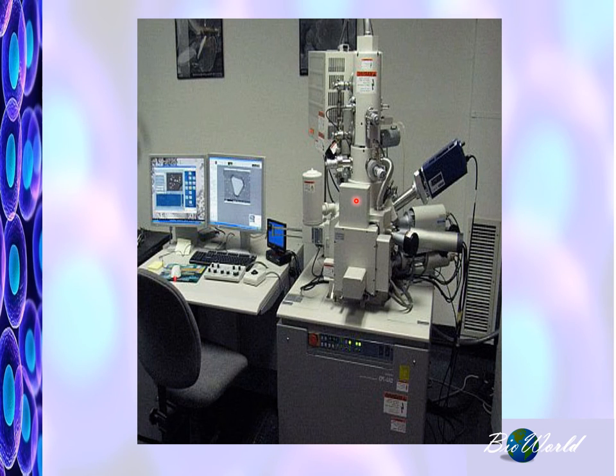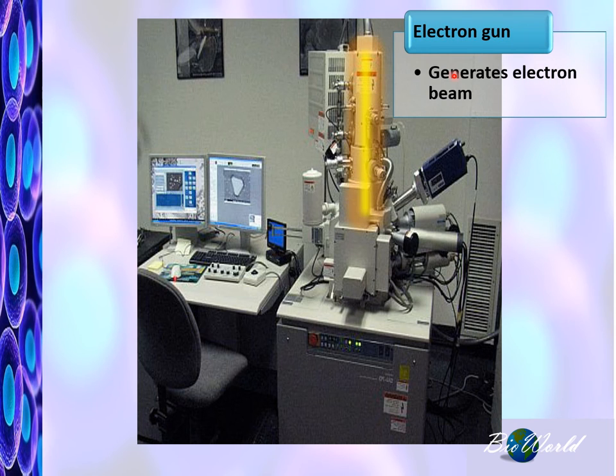The scanning electron microscope in the early stages is similar to the transmission electron microscope. So when you switch it on, an electron gun will generate the electron beam. That electron beam will contain electrons traveling at high speed. So this column will be a vacuum also. Then you'll have the magnetic condenser lenses focusing the electron beam onto the specimen.